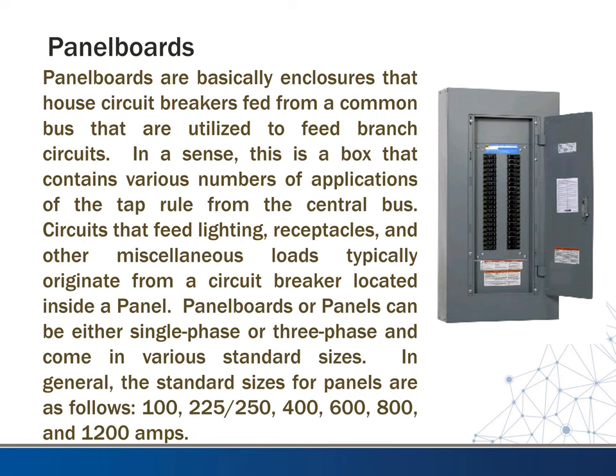So first we want to talk about panel boards. So panel boards are basically enclosures that house circuit breakers fed from a common bus that are utilized to feed branch circuits. So in a sense, this is a box that contains various numbers of the application of the tap rule from the central bus. Circuits that feed lighting, receptacles, and other miscellaneous loads typically originate from a circuit breaker located inside a panel.